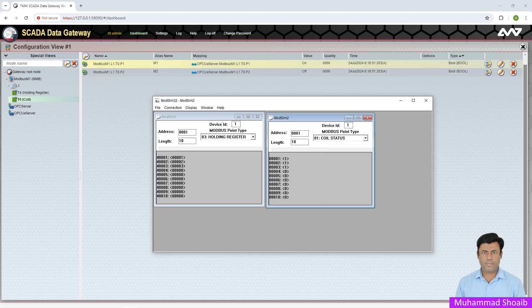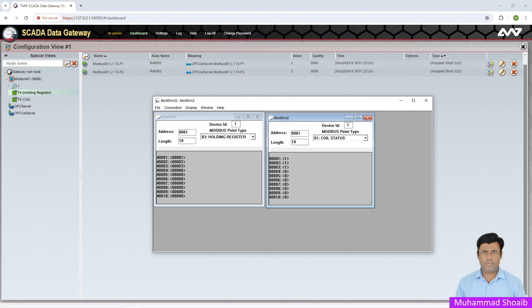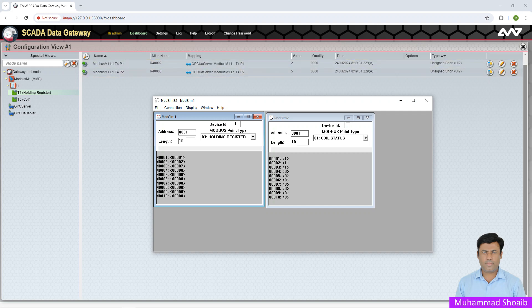As you can see, the first coil is on and the second is also on. In the holding register area, the data is perfectly updating. I'll set an auto-simulated value. As you can see, whatever data is inside the Modbus slave device, the same data is in the Modbus master device. This means the Modbus slave and Modbus master are communicating with each other, and data is coming into the SCADA Data Gateway application. The first step is successfully completed.